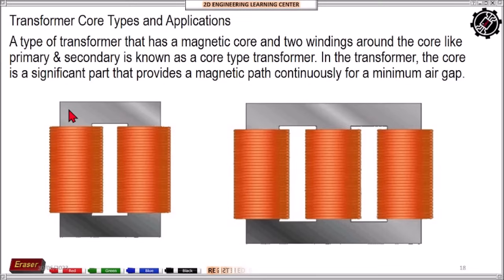Next, the applications of core type transformer include the following. These transformers are suitable for high voltage range applications like power distribution and auto transformers, because high voltage simply corresponds to high flux. So a thicker core is used to keep iron loss down, making this transformer a good choice - it's better for high voltage application because its core is thicker, therefore it could maintain a lower iron loss.